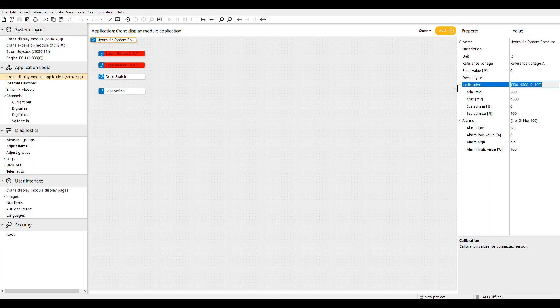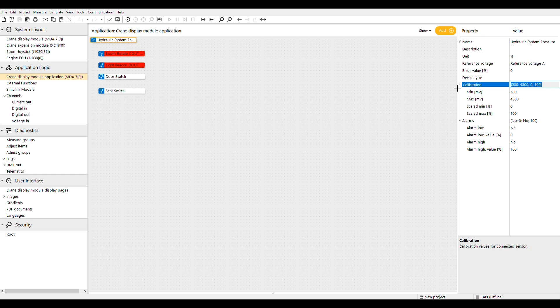This input is currently set up as a ratiometric sensor where instead of the full range of 0 to 5,000 millivolts, it's set for 500 to 4,500 millivolts to allow for open or short circuit detection. This range is then scaled 0% to 100%. Scaling can also be done using math function blocks within the program.